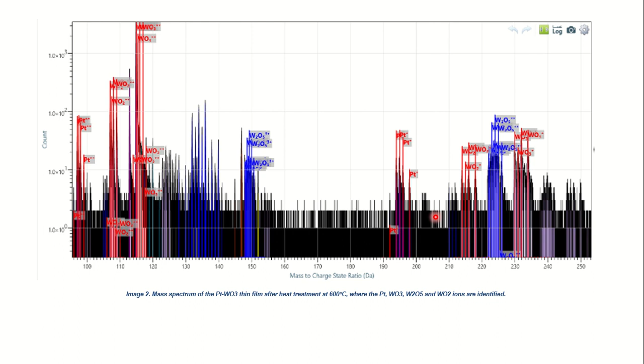Given this, it is possible to identify the ions of each element because, depending on the charge of each one, the mass-to-charge ratio changes. This can be shown in the image as we can look at platinum with charge 1, and then here we can look at platinum at charge 2, and also we can look at tungsten trioxide with charge 1, and then moving to the left we can look at it with charge 2, as well as WO3 and tungsten dioxide.